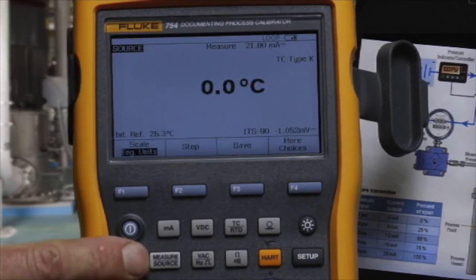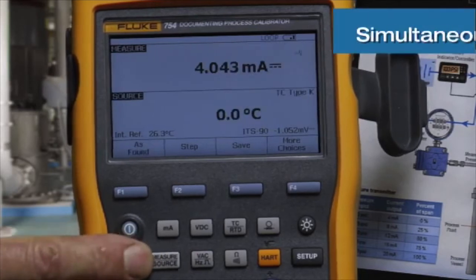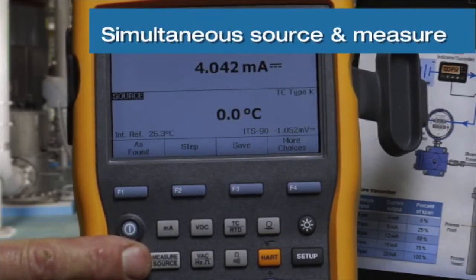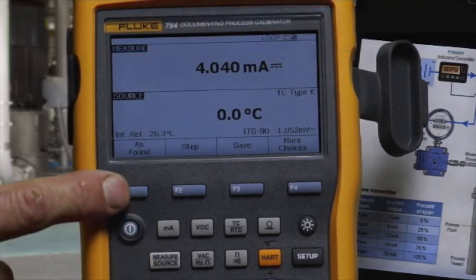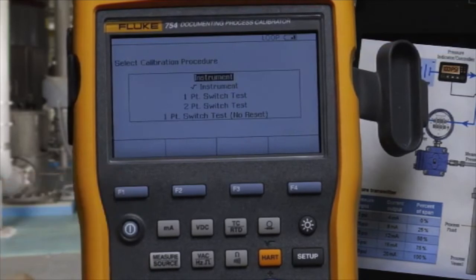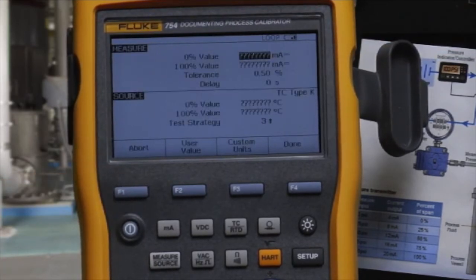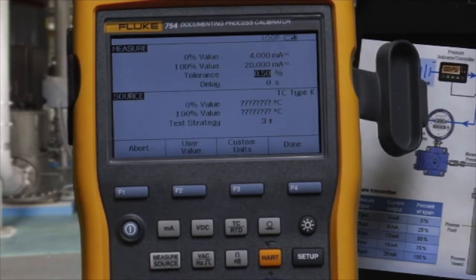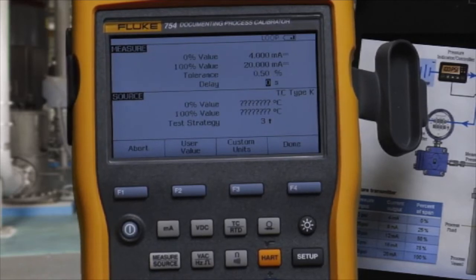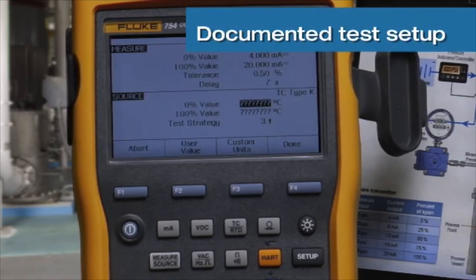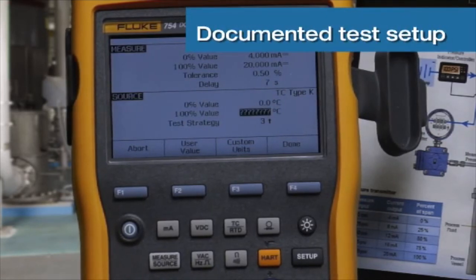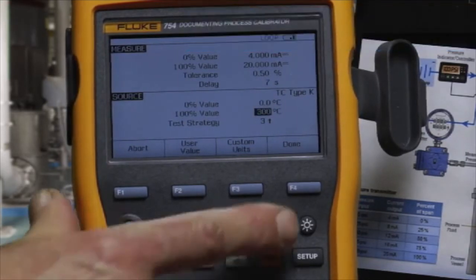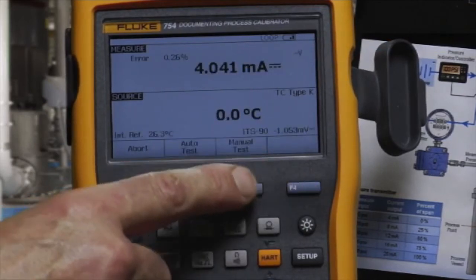Enter the split screen to do the calibration test. Select as found for an instrument. Configure what we're going to measure, 4 to 20 milliamps. 0.5 percent. Set settling delay, and source 0 to 300 degrees C and a three-point test.